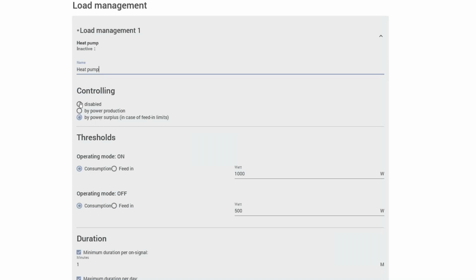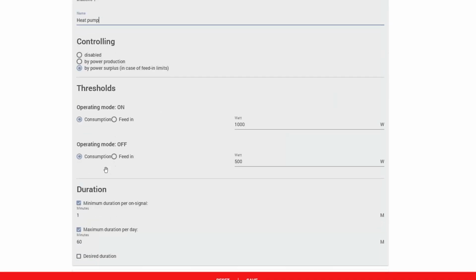You can disable it, that is, if you don't want to implement it, or you can enable it by power production or by power surplus. By power production simply means that so long as your PV is generating, the heat pump will be turned on. This usually is not very economical per se, but it depends on the priority of function. The choice normally implemented is power surplus. This means that once your base load has been sufficiently supplied and you are generating more than you are consuming, you can use the surplus power to trigger your heavy loads, in this case labeled heat pump.